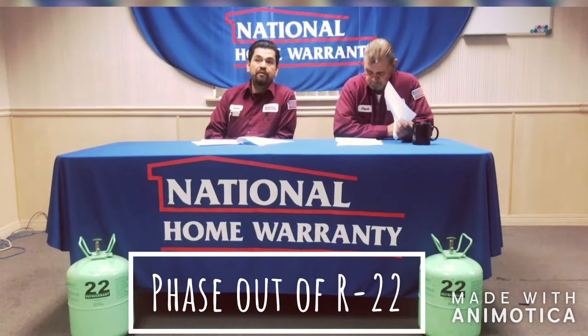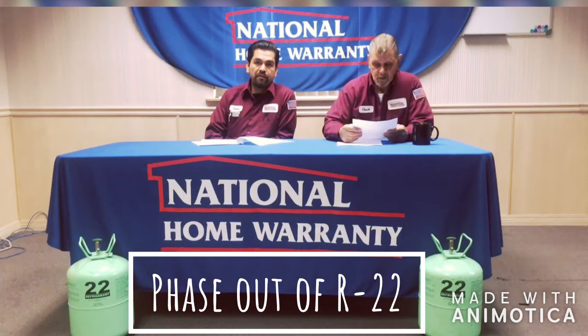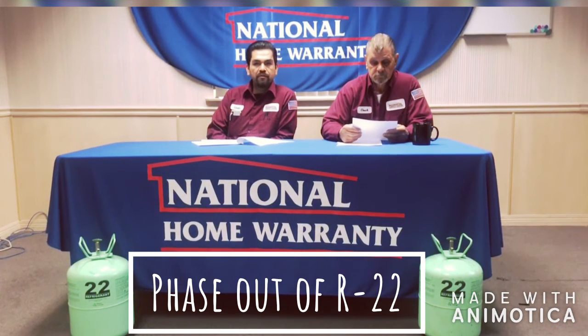During your scheduled preventive maintenance appointment, we inspect and clean the condensate drains, the heat exchanger, the condenser coil, the ignition assembly, the blower components. We inspect safety of the system, the defrost mode, the blower assembly, the heat mode, proper refrigerant levels, electric heat strips, all motors, capacitors, air filters, thermostat calibration, vibration noise. We also measure the refrigerant pressures, the temperature difference in the supply and the return, volts, amps, and the heating cycle. And we lubricate all moving components.